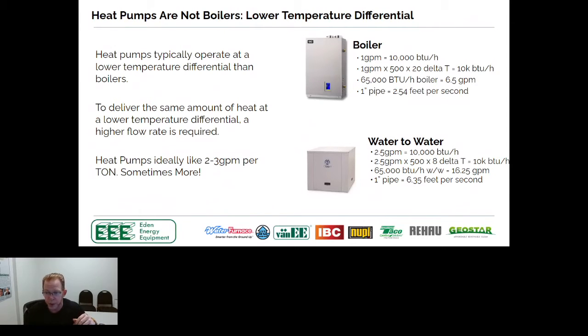Redo the math with an appliance that has a maximum of 8-degree delta T. In this scenario, typically it's around the 4 to 5 range. I picked 8 just to be as generous as possible, and we can see that 65,000 BTUs is actually 16 gallons a minute. Well, 16 gallons a minute going through 1 inch pipe, not a great idea. What ends up happening is we have a unit that's not performing very well. We don't have enough flow going through that unit.